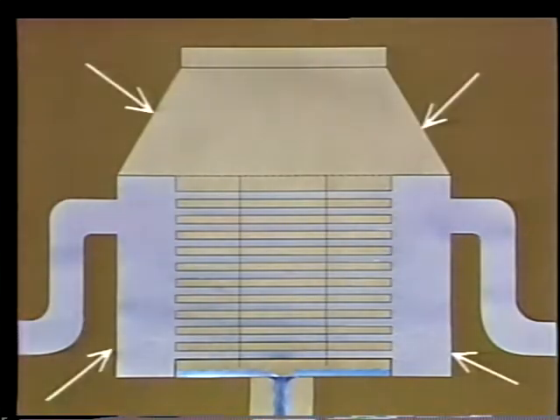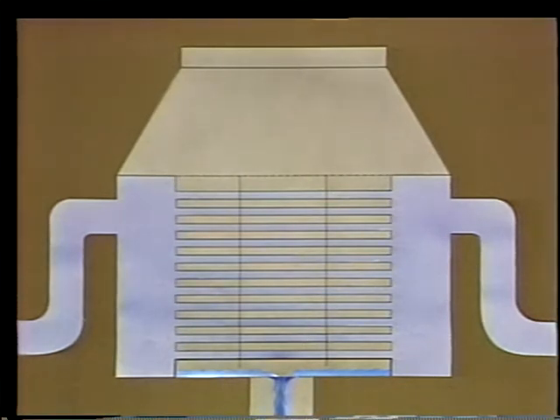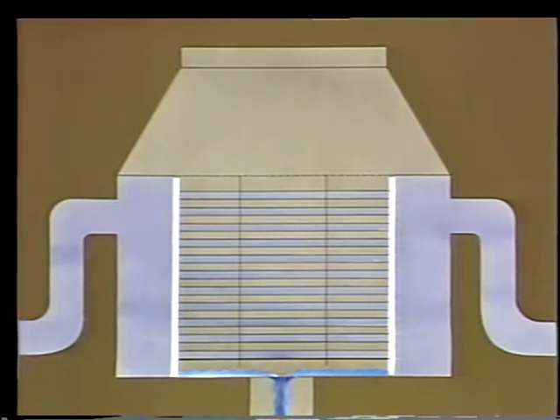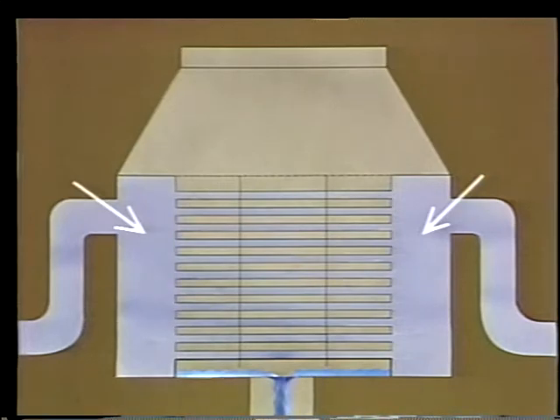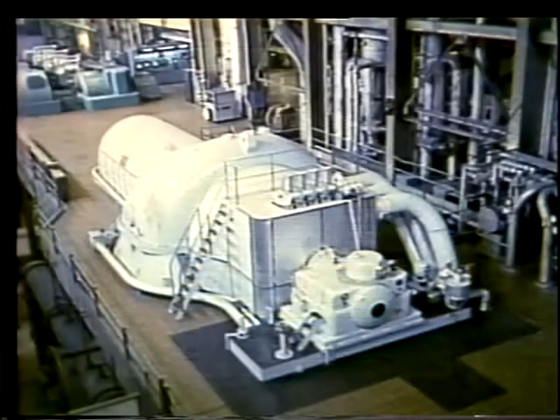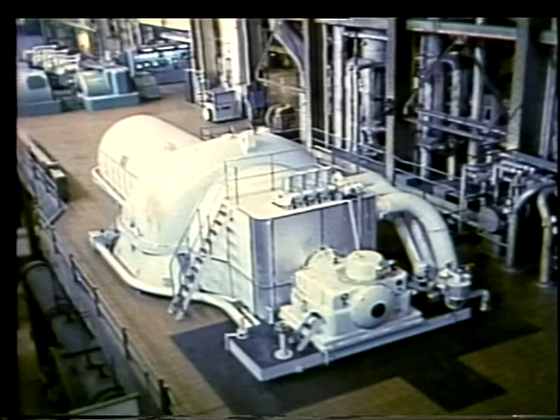Let's take a closer look at each one of the three we're considering: condensers and shell and tube heat exchangers, which are surface types, and direct contact heat exchangers. A condenser is made up of a shell, which is the main part of its structure. This holds the sheets to which the tubes are attached. The tube sheets at each end support the tubes and isolate the water boxes from the rest of the shell. Ordinarily, a large steam-driven turbine used to drive a generator or a pump has a condenser right beneath it. The turbine exhausts steam into the condenser where it gives up heat.